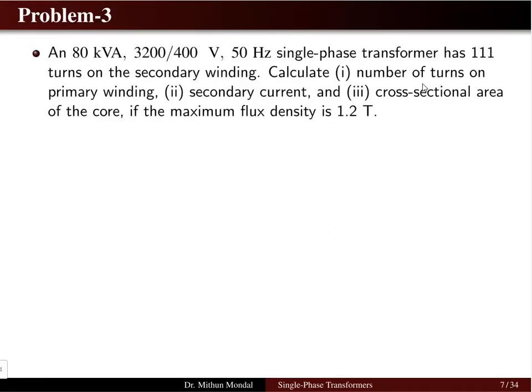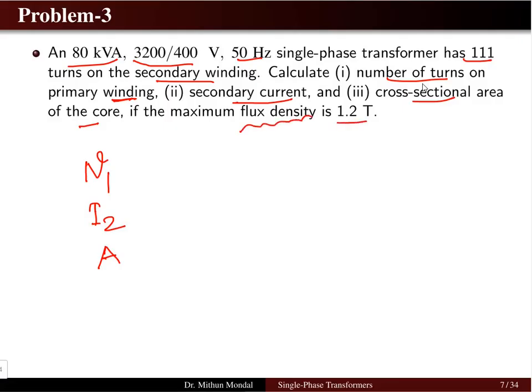In the third problem, we have an 80 kVA transformer, the voltage rating is given as 3200 by 400 volt, 50 Hz, and the turns given are 111 turns on the secondary winding. We have to determine the number of turns on the primary winding, N1, the secondary current I2, and the cross-sectional area of the core, given that the flux density is 1.2 Tesla. Note that the current we are finding, I2, is the full load current, because we will be finding this current with respect to the full load kVA rating of the transformer.